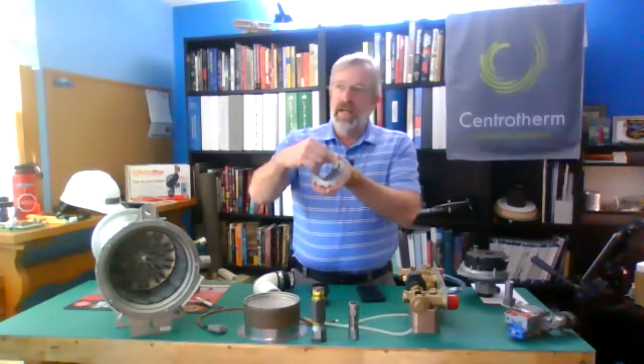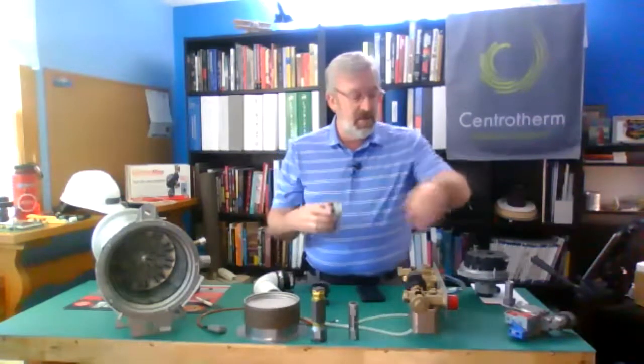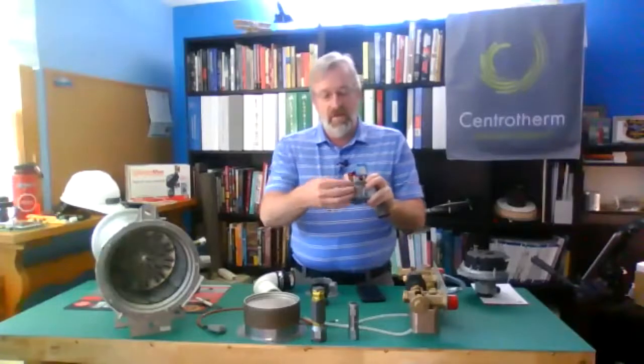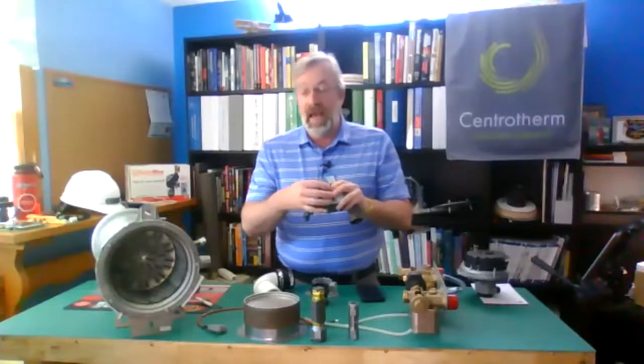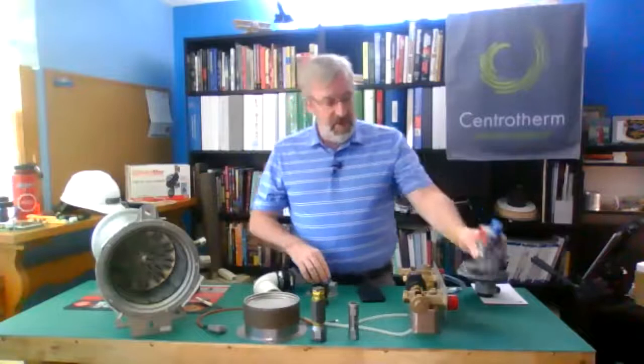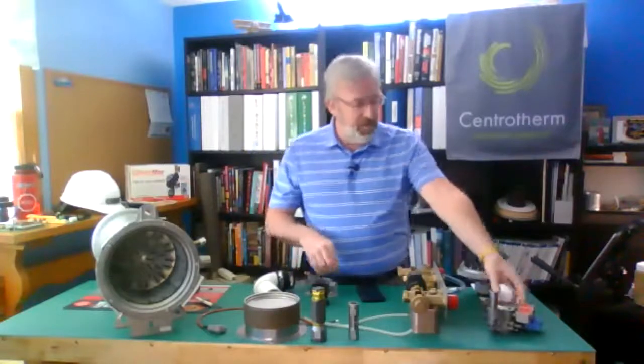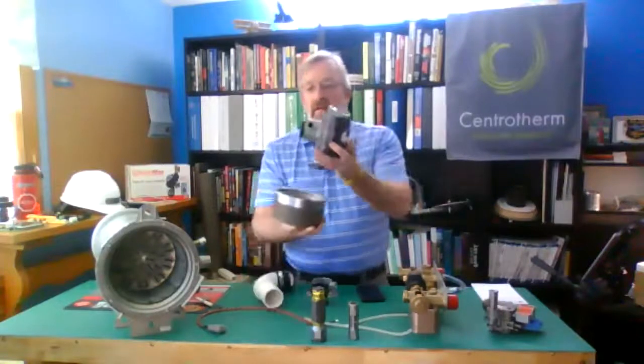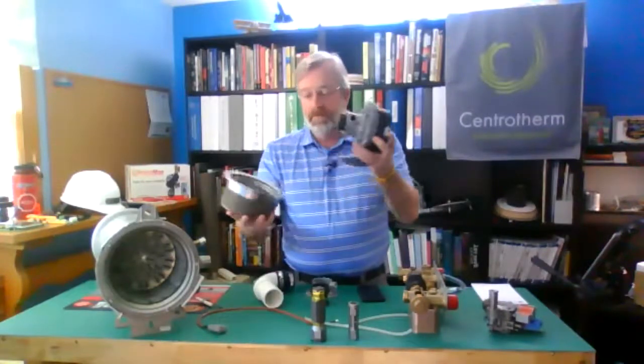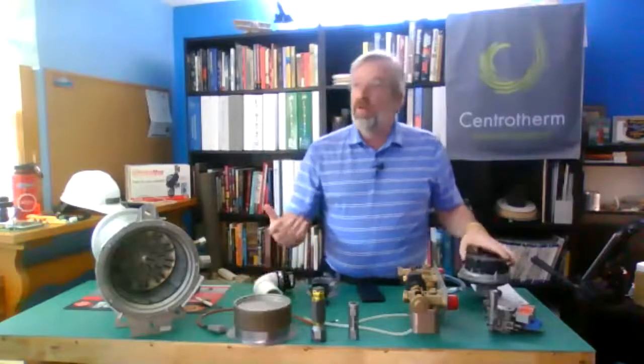That negative pressure is here on the inlet side of the venturi, which at the end of the day connects over to my gas valve. So I create that suction, my gas valve opens, I use the fan to draw through the amount of air and the amount of gas that I need, dump it in through my orifices of my venturi, into my fan, and it puts it into the burner. Set off a little spark, and hopefully we get flame, and everything's nice and happy right there.